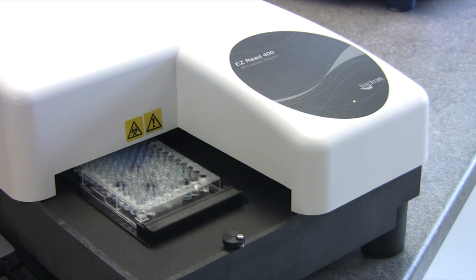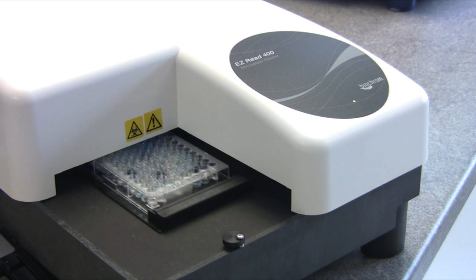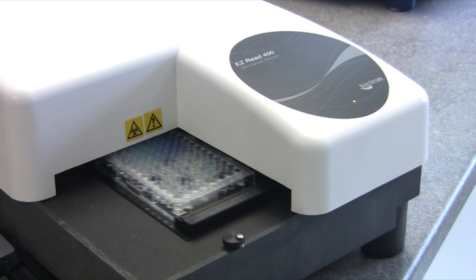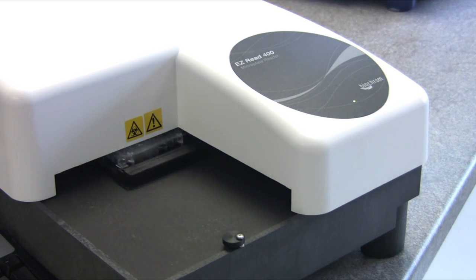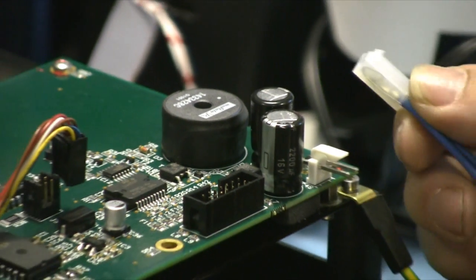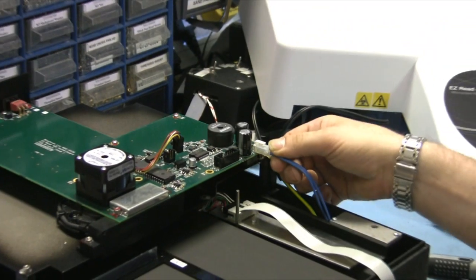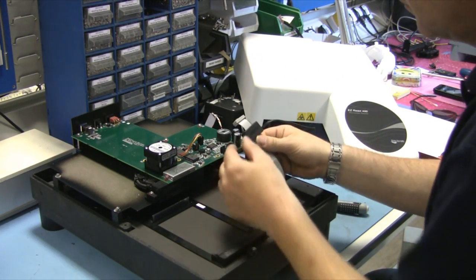There are three models of the EZ Read 400 addressing customer needs in different laboratory environments. The EZ Read ELISA reader was specifically designed for laboratories that require a robust and reliable reader for ELISA assays. The EZ Read Research was designed to meet the needs of a multi-use laboratory, offering eight pre-installed filters providing the ability to undertake ELISA, protein and cell proliferation assays. The EZ Read Flexi is a bespoke model for labs with specific and unique application requirements.